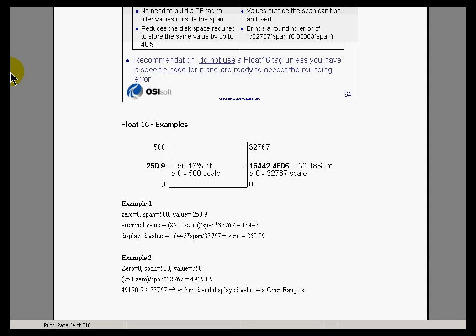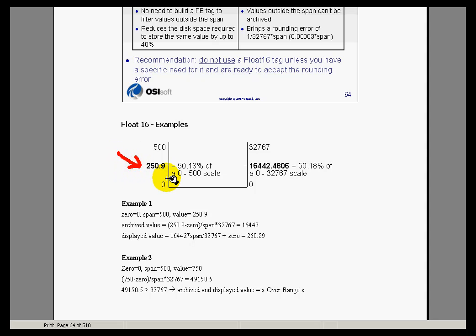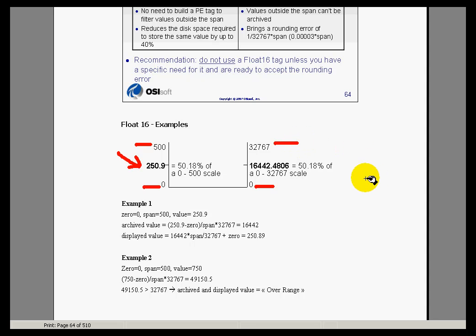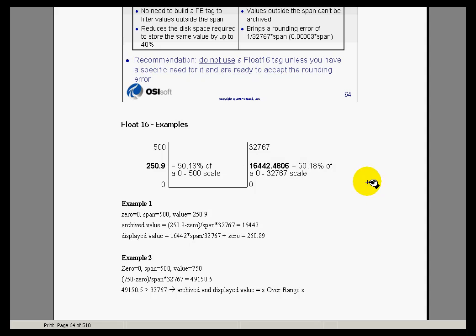Here's an illustration from your notes that describes exactly what's going on with a Float 16. When you get a value that's a real number — for example, 250.9 — that's not how we're going to store it. We look at where that falls on the scale of the instrument, 0 to 500, figure out that it's 50.18% of the range, and map that to the range of 0 to 32,767, which is 2 to the 15th. So 50.18% ends up being 16,442. But since we're storing this as an integer, you have a rounding error. The rounding error is equivalent to the span times 1 over 32,767, or in other words the span times 3 one-hundred-thousandths.